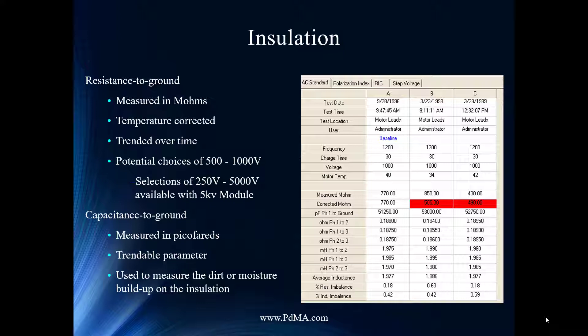The main variable affecting insulation resistance is temperature. Insulation has a negative temperature coefficient — raise the temperature and resistance drops; lower the temperature and resistance goes up. That variability makes trending very difficult. Temperature correction gives you a number that's more trendable, so whether you test in winter or summer, by recording the actual temperature you get a comparable, trendable value.